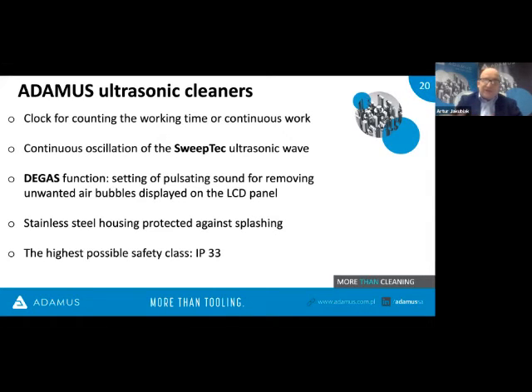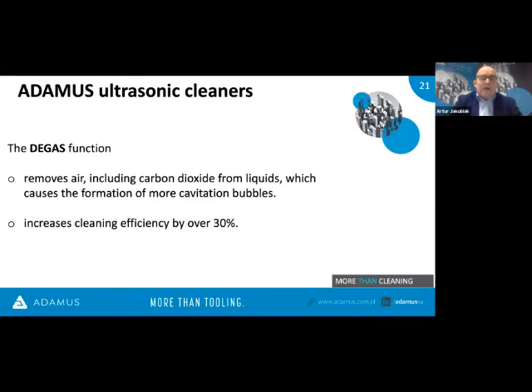We have a special lid which is protected against splashing, and of course, we have the highest possible safety class, IP33, for all our equipment for the ultrasonic cleaners. Just one sentence more about the degas function. It removes air, including carbon dioxide, from the liquids, which causes the formation of more cavitation bubbles. So, as I said, we need to remove all these unwanted gases just to increase the formation of cavitation bubbles, which we need for the cleaning. This degas function, as you see, increases cleaning efficiency by over 30%. So this is a really good gain when we degas the cleaning solution.